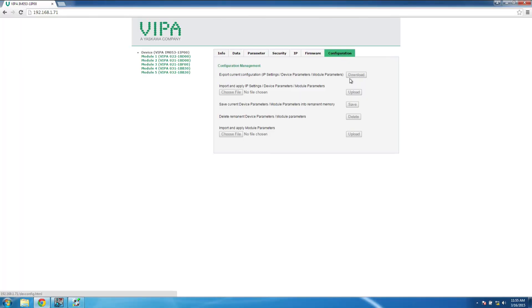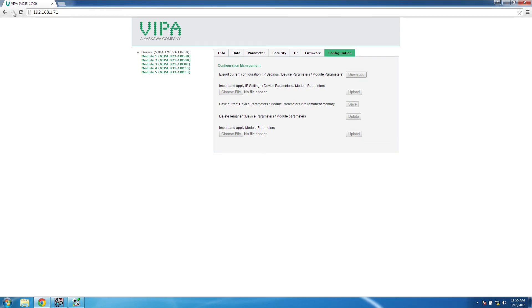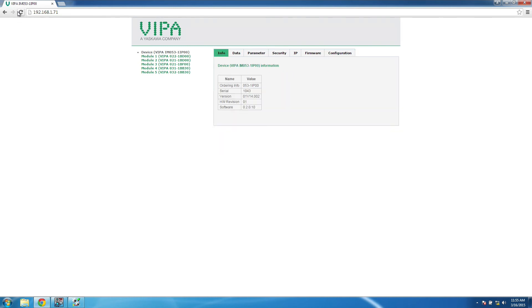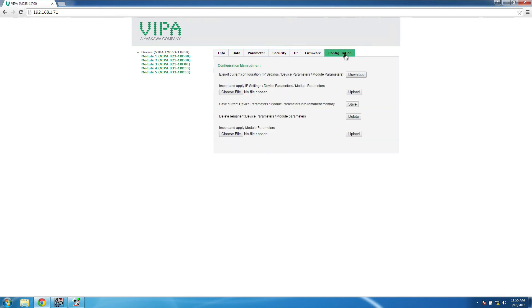It is important to point out that all the controls on the webpage will be unavailable once the bus coupler connects to the PLC. You can disconnect the bus coupler from the PLC, then cycle power in order to be able to access these controls once again.